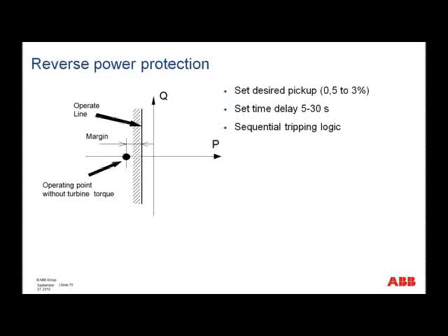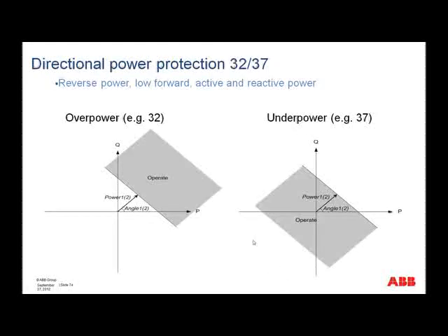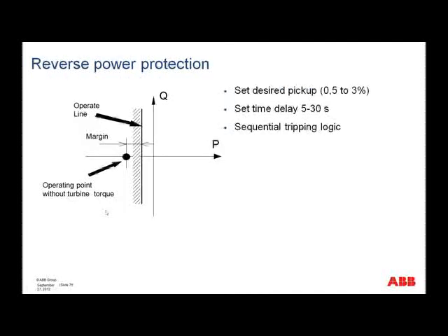One way then of detecting that we're not producing active power is to have this reverse power protection. Now, if you think of this here, this would be an over power protection, but with this swung around so this angle is 180 degrees. And in this case, this would give you the operate line here. So the operate area would be this side, and this would be set with some margin, because here would be the operating point of what would be the power into the generator without the turbine torque.